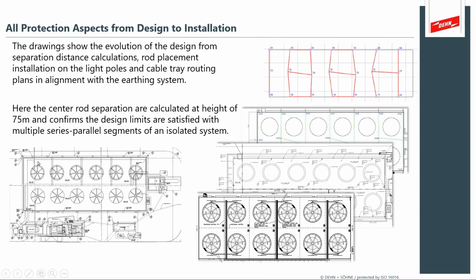And off to the left, we can see that this all has to be coordinated so that the down conductors on such a large structure come down onto the pigtails that are going to be on the earthing system around it. And so here you see an earthing system mesh as part of the interconnected structure that's buried in the ground. And then the pigtails emerge from the soil, and that's where we want to have our down conductor bond into the earthing system.